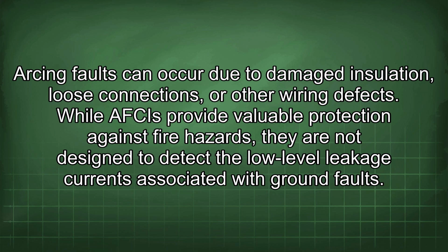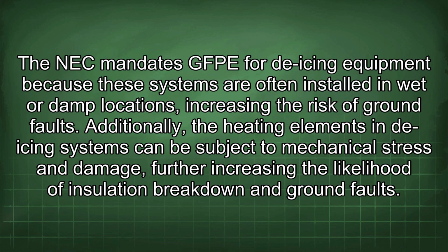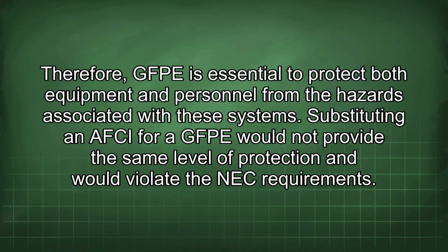ground faults. The NEC mandates GFPE for de-icing equipment because these systems are often installed in wet or damp locations, increasing the risk of ground faults. Additionally, the heating elements in de-icing systems can be subject to mechanical stress and damage, further increasing the likelihood of insulation breakdown and ground faults. Therefore, GFPE is essential to protect both equipment and personnel from the hazards associated with these systems.